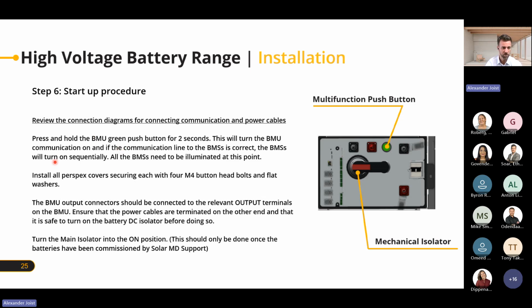That's quite important. Then you can press the green button on top and hold it for 2 seconds, and the BMU will turn on and communicate with all the BMSs, and we'll be able to see all BMSs starting up and communicating. If you see one BMS not communicating, we can do some troubleshooting, but all BMS units need to illuminate at this point. Once you see that, you can install all the Perspex covers and secure the front, so you have some touch protection on the battery, and move on from there.